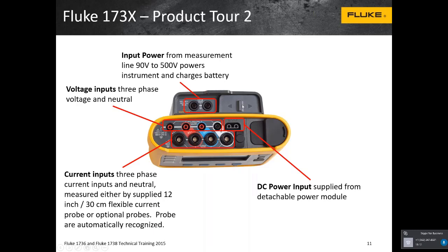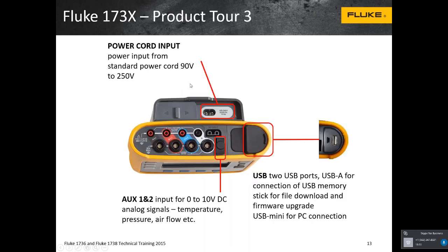You can slide the switch over to reveal a 120 volt input, which uses a regular power cord. Or you can slide it back to expose two banana jacks, which cable into the voltage lead assembly, allowing you to supply power using up to 500 volts. So if you have a 480 volt system, you can use that for power and don't need 120 volts there. That's something that's been added, and the slider just slides back and forth to switch between one or the other, exposing the power cord input when switched over.